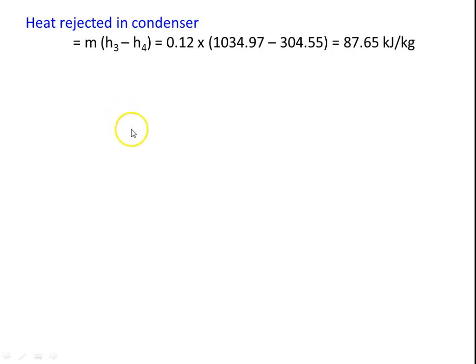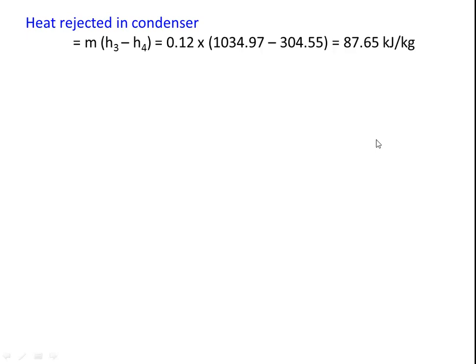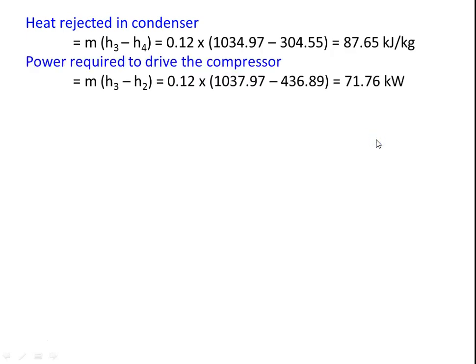Heat rejected in the condenser = M × (H3 - H4) = 0.12 × (1034.97 - 304.55) = 87.65 kJ/kg. Power required to drive the compressor = M × (H3 - H2) = 0.12 × (1034.97 - 436.89) = 71.76 kW.